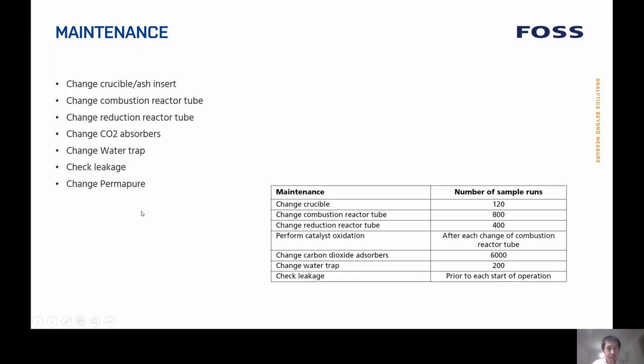And there's another consumable, the PermaPure. The PermaPure has a lifetime of about 2 years. It's maintenance free, so you don't need to change it frequently, but it is also part of the maintenance.